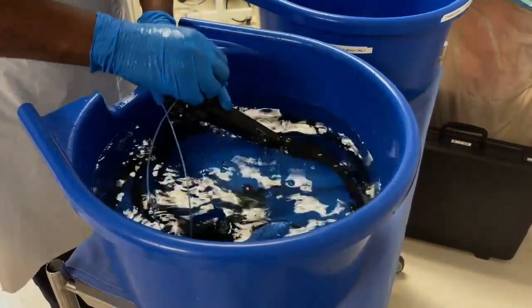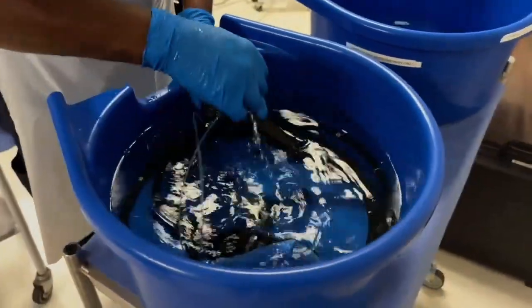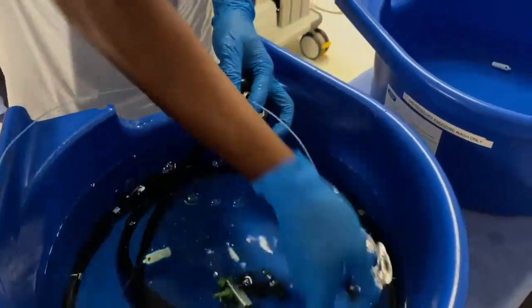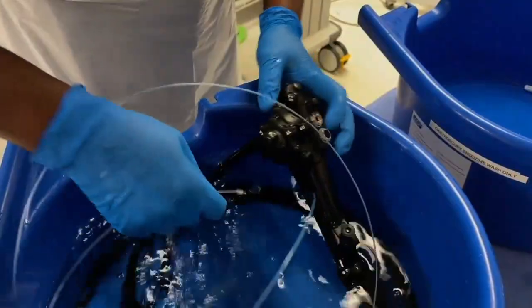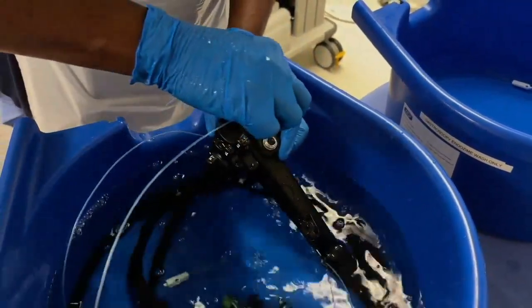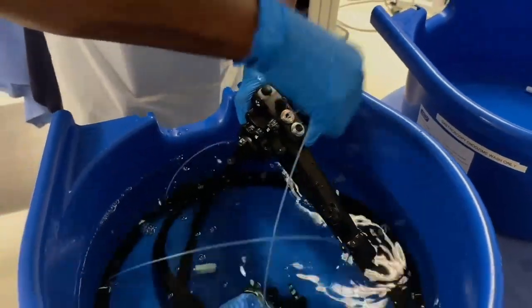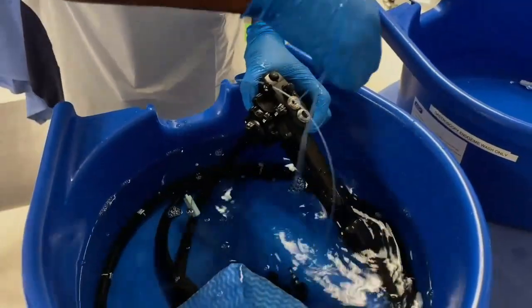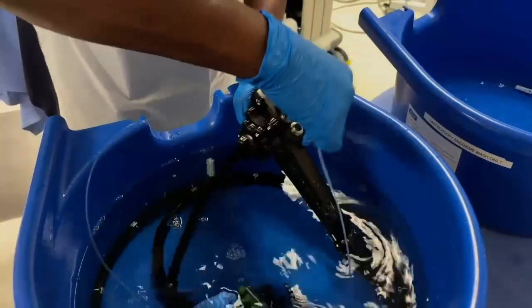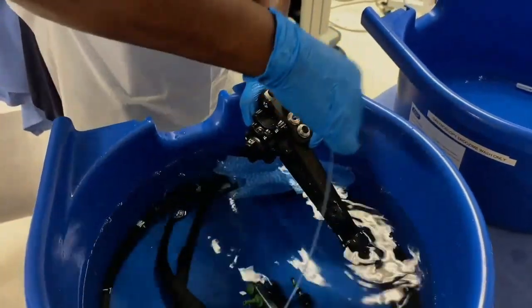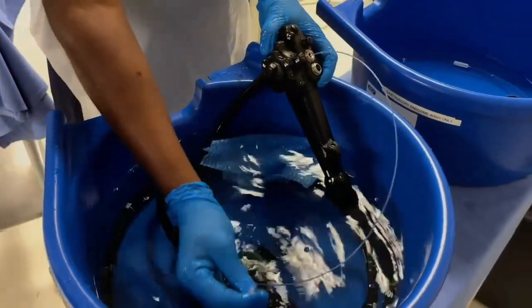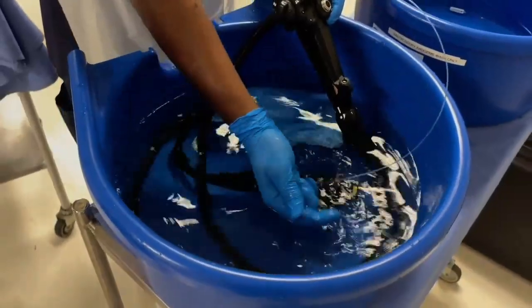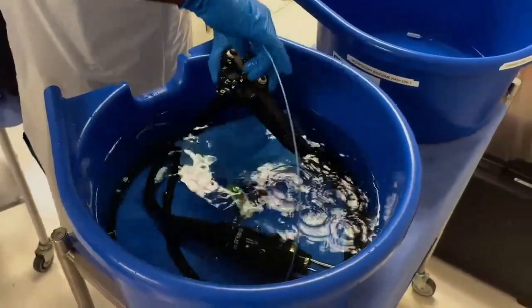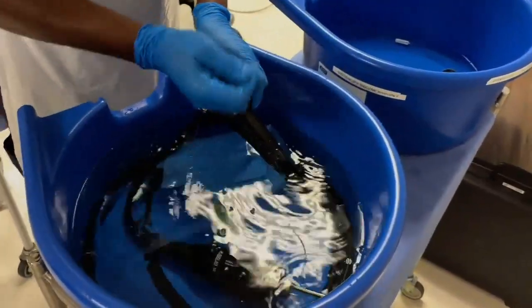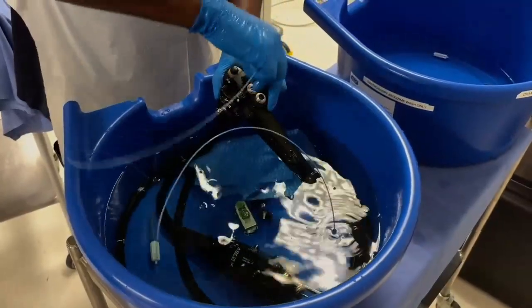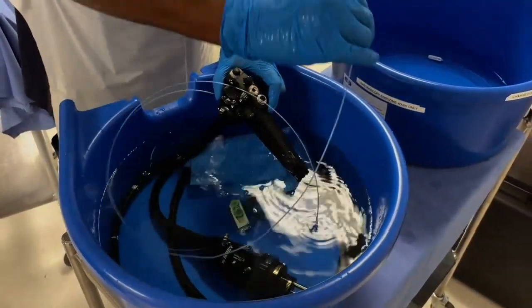Make sure you have the right size diameter of brush. And here you can see we are beginning to insert the brush to clean the ports and the channels. Our technician inserts the brush and is cleaning with a back and forth motion. A back and forth motion has been shown to be very effective, as well as a spinning motion. Importantly, the technician looks at the tip of the brush as it comes through the scope to make sure that it is clean. He rinses that tip and cleans whilst removing that brush again.